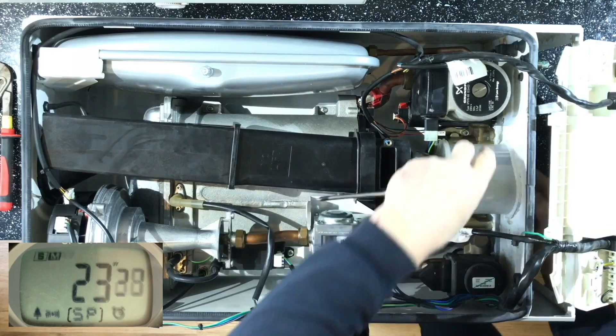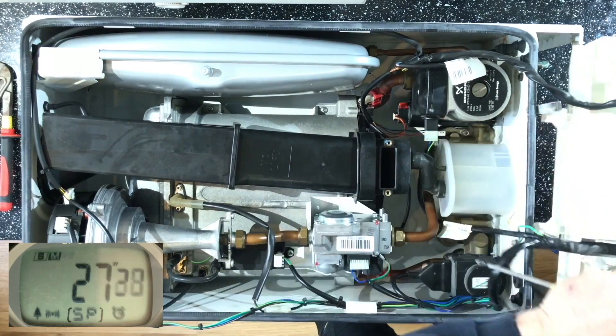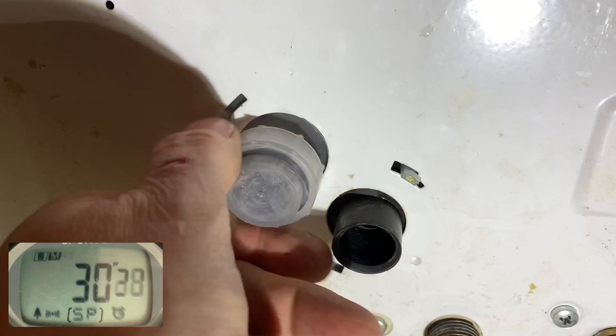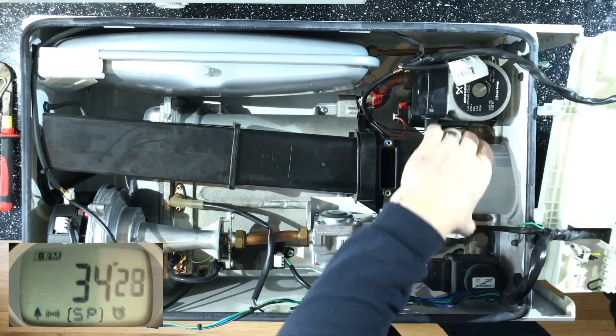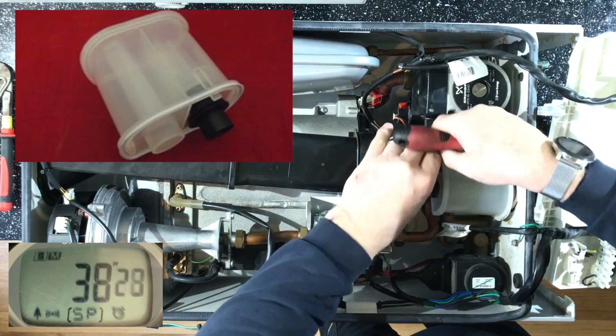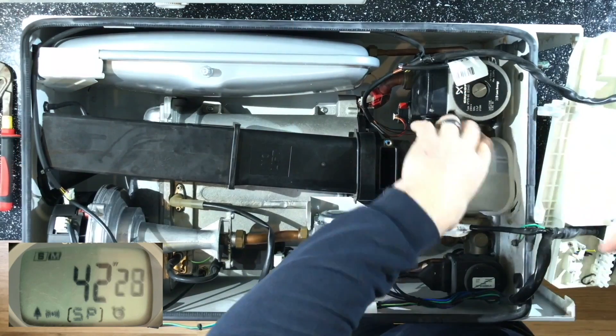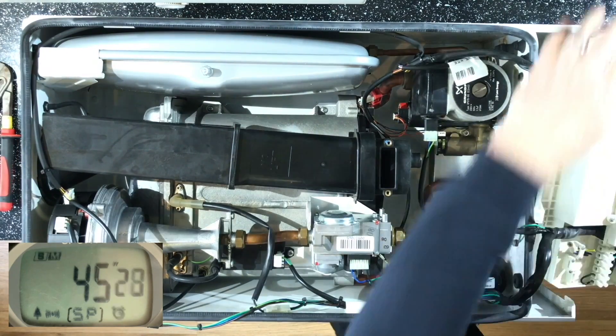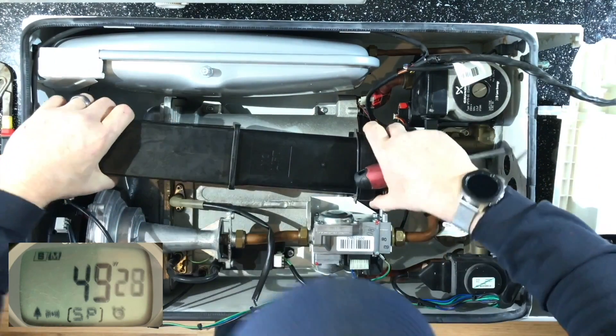The next thing I'm removing is the condensate trap. Now this is one of the old traps, and it has a retaining nut on the bottom here which I'm taking off, which holds the condensate trap in position. In the new ones, this doesn't exist now, it's just a plastic cover which is molded into the trap itself. Now I can start taking off this manifold.